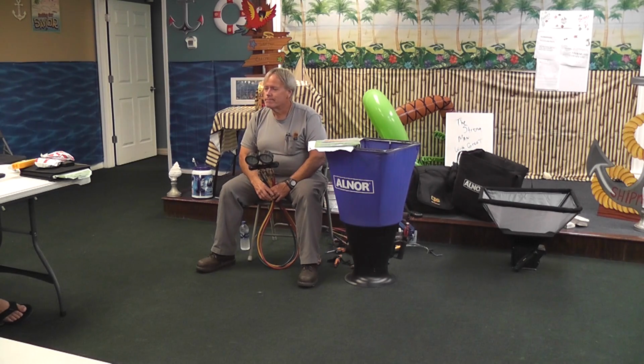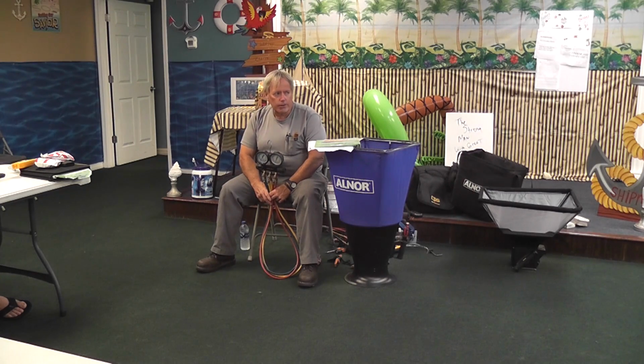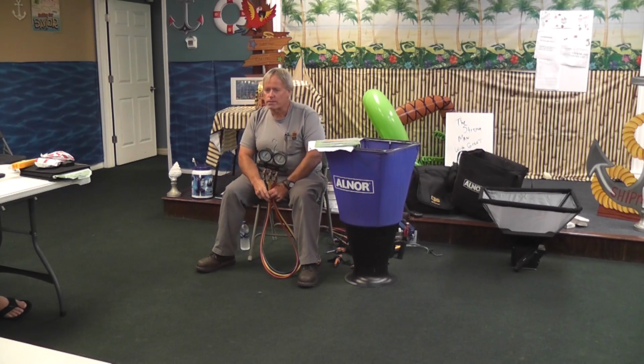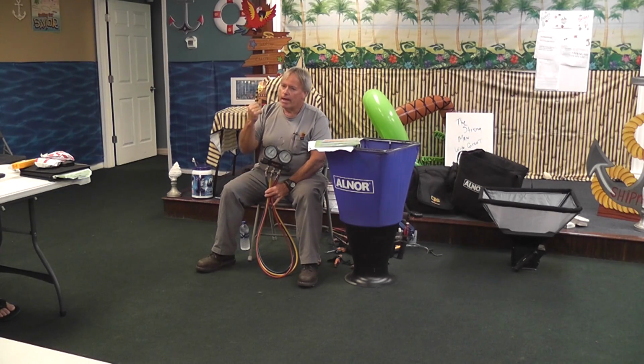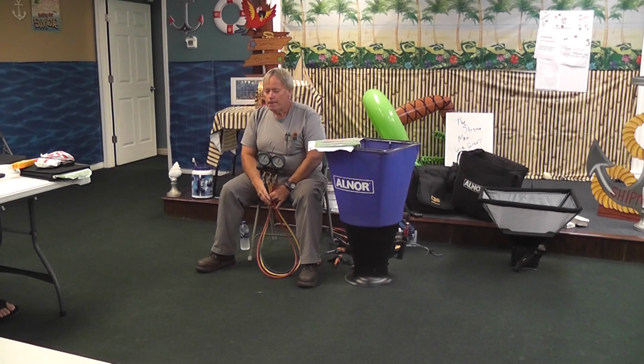Pull the charge out, evacuate, pull the charge out, change the dryer, evacuate it, and recharge with new refrigerant, and the problems go away. You can't mix refrigerants. Most of the refrigerants on the market today end in an A, and it's a blend. And when you charge it, you have to charge liquid. If you charge gas, you will ruin a whole tank of refrigerant because it fractionates. It's made up of multiple gases that have different boiling points, and when you turn a valve off, all that liquid refrigerant boils off, and it lets off a different amount of gas as it goes. So if you charge a machine with vapor off the top of the tank and don't turn it over, you won't get the right blend, and you just wasted a tank of refrigerant.